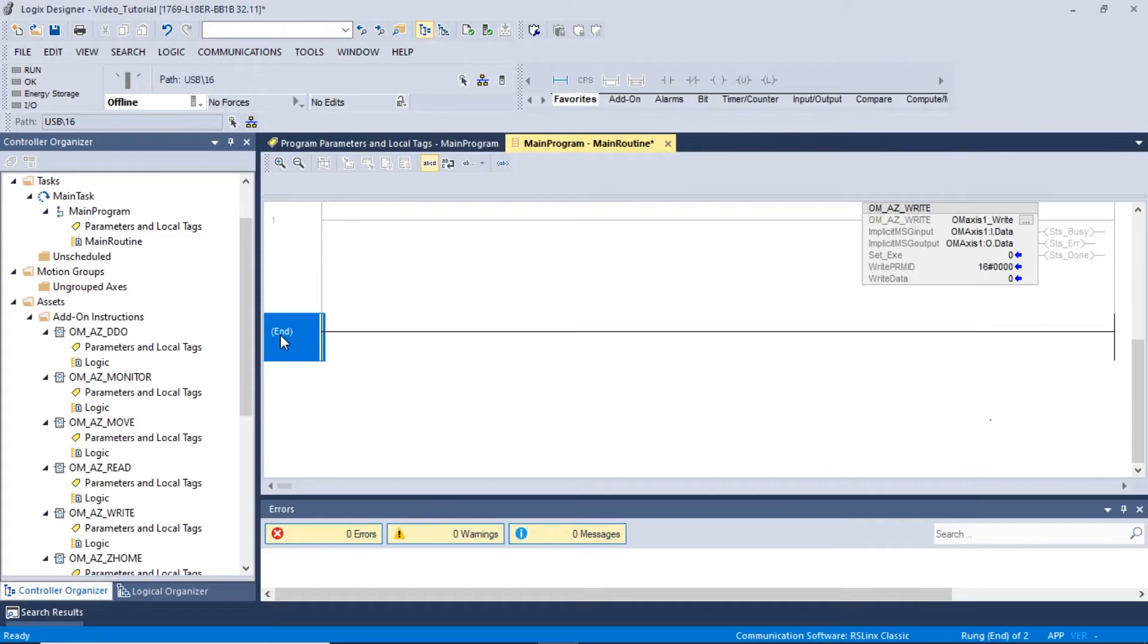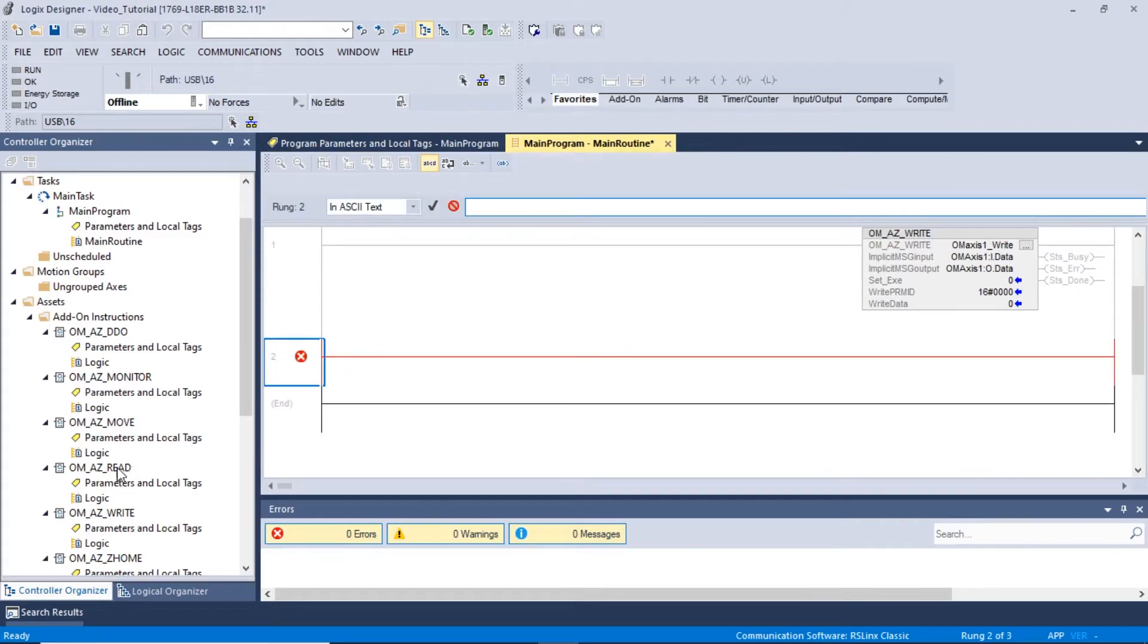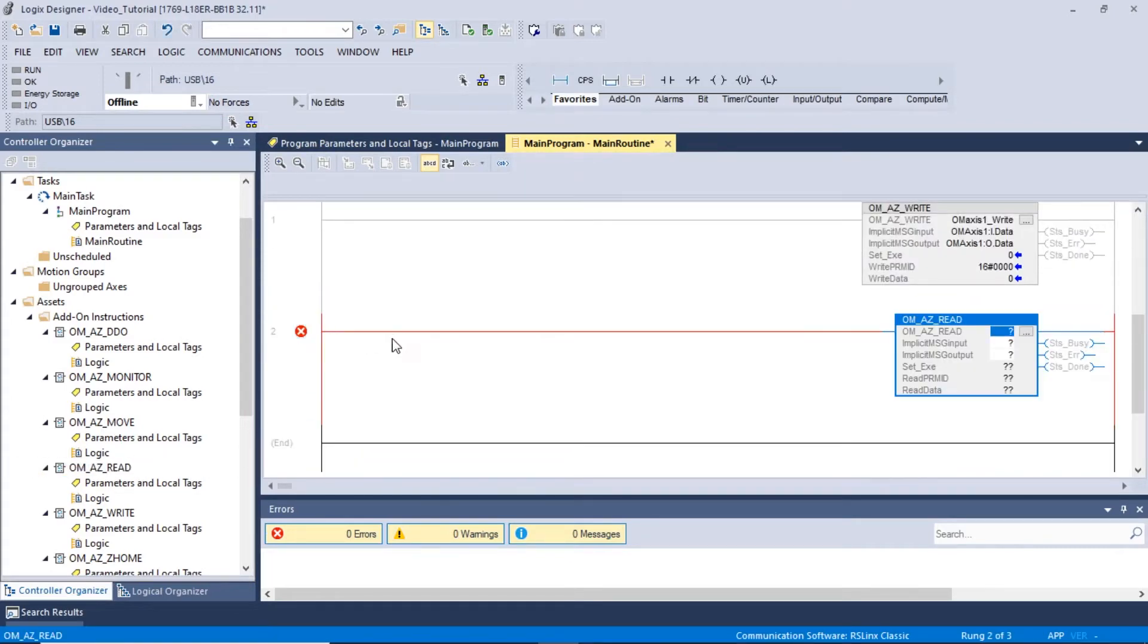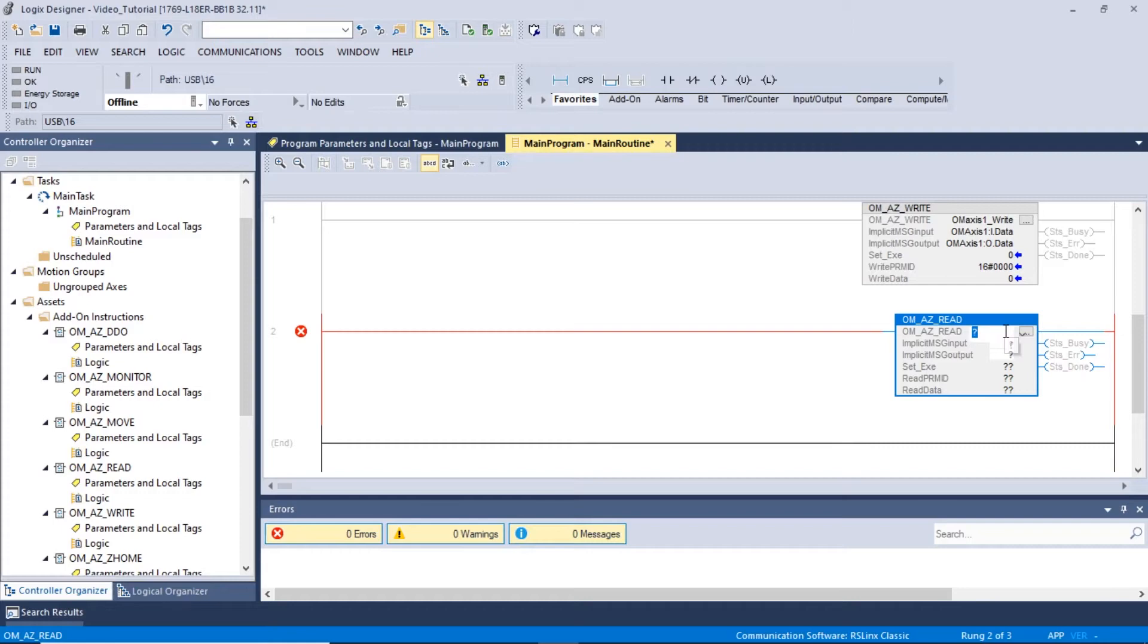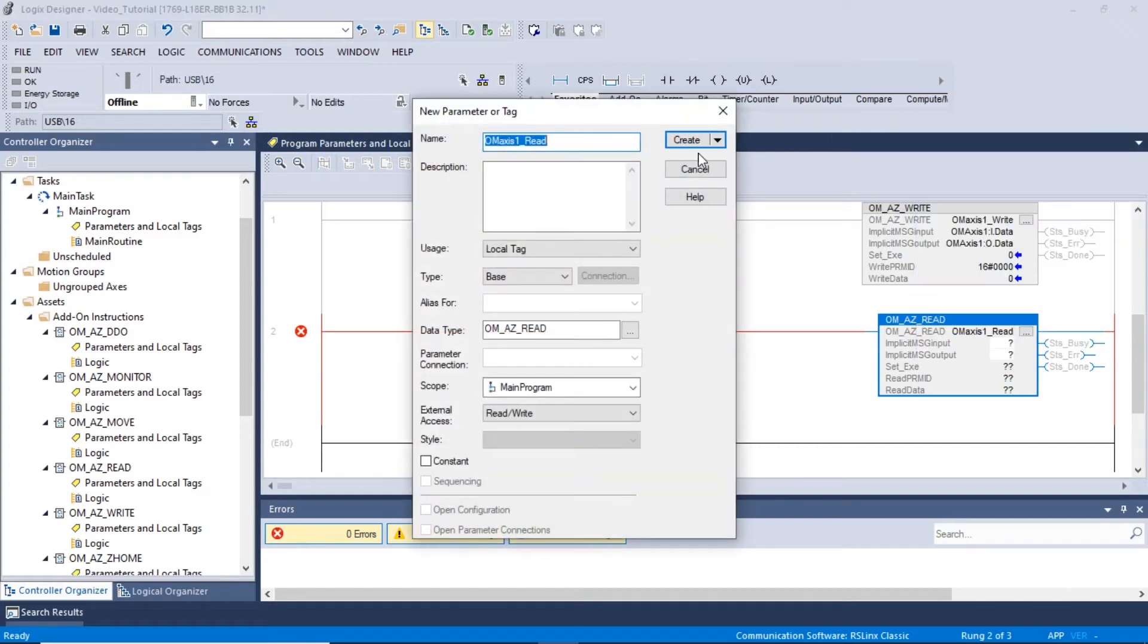Expand the Assets folder and drag over the OMAZReadAOI. The local tag for the AOI can be set by double-clicking the first box. In this example, we will name the AOI tag OMAXIS1Read. Right-click the created tag and click New Tag. A new window will appear displaying the new tag. Click Create to proceed.